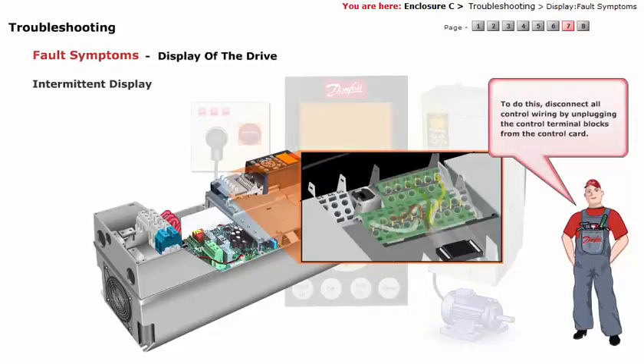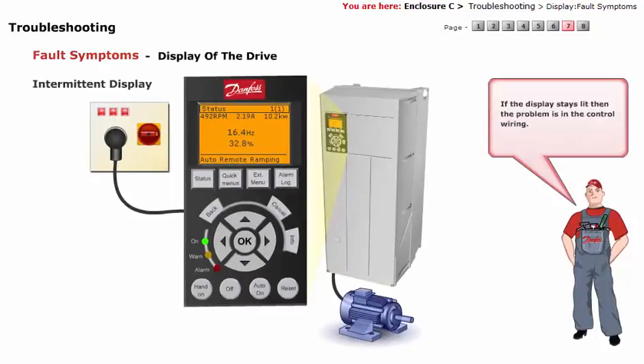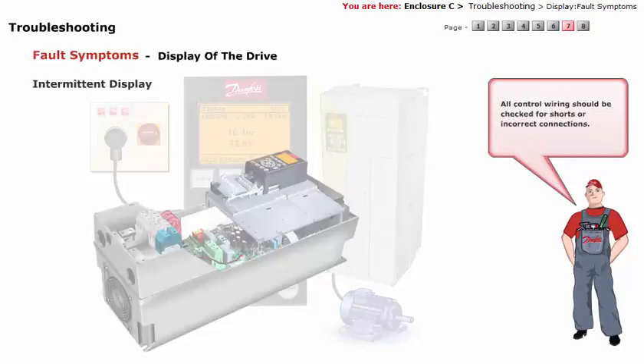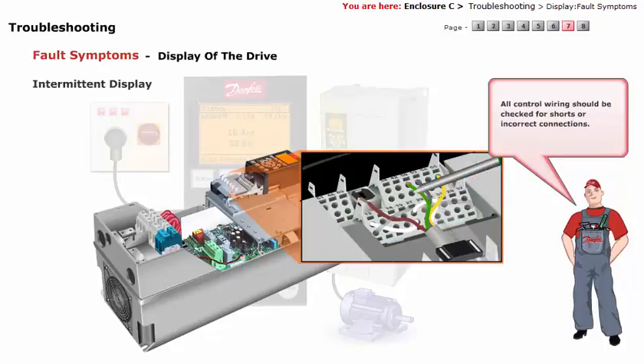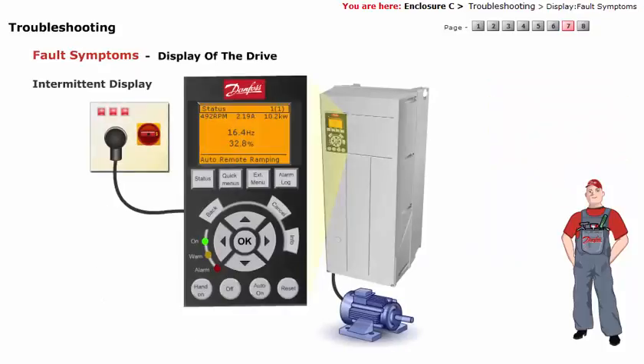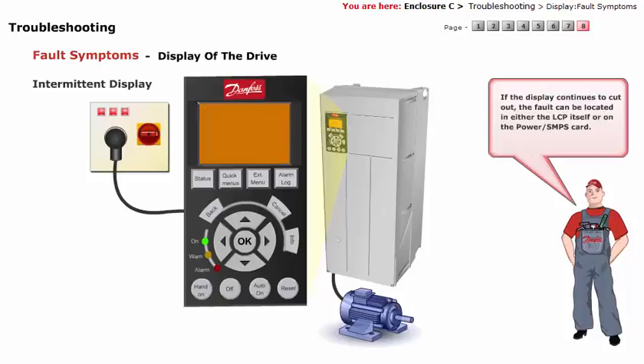The first step is to rule out the problem in the control wiring. To do this, disconnect all control wiring by unplugging the control terminal blocks from the control card. If the display stays lit, then the problem is in the control wiring, and all control wiring should be checked for shorts or incorrect connections. If the display continues to cut out, the fault can be located in either the LCP itself or on the power or SMPS.